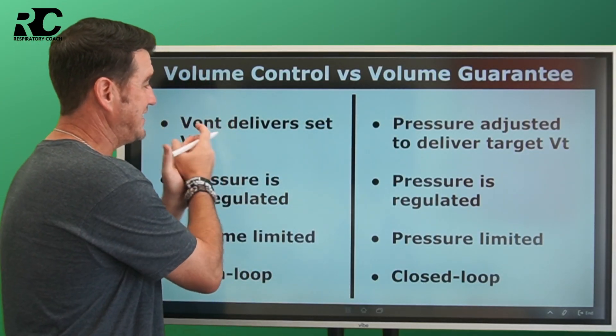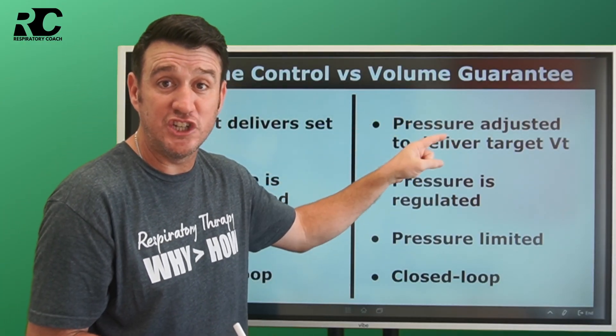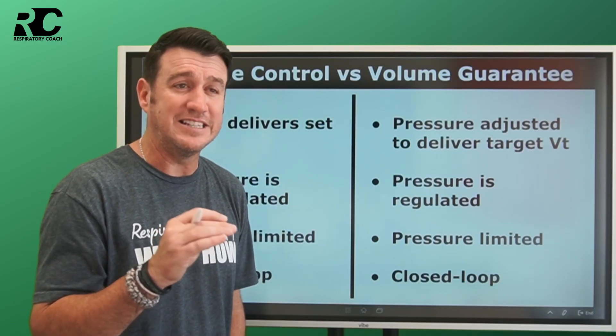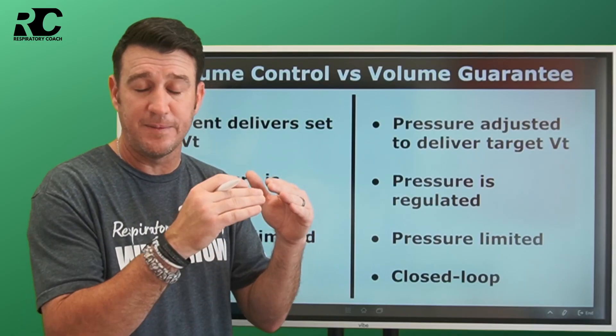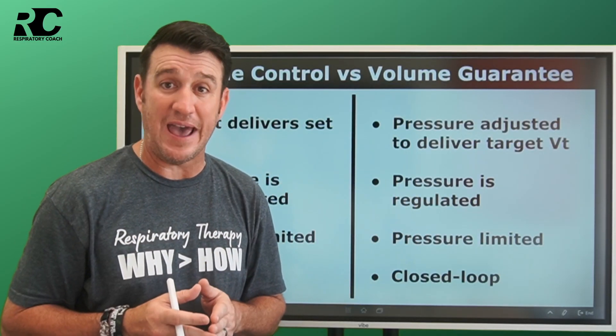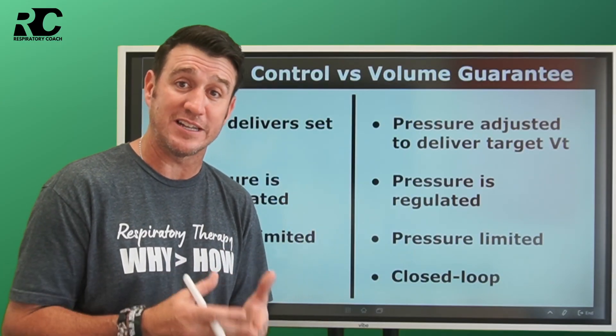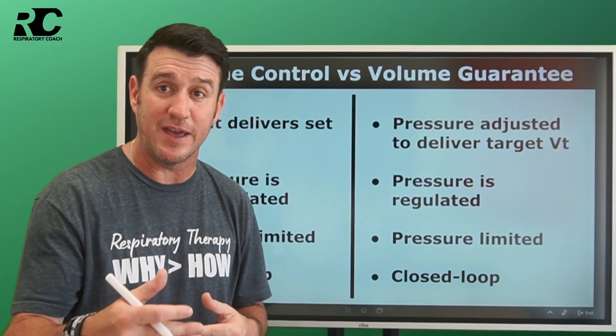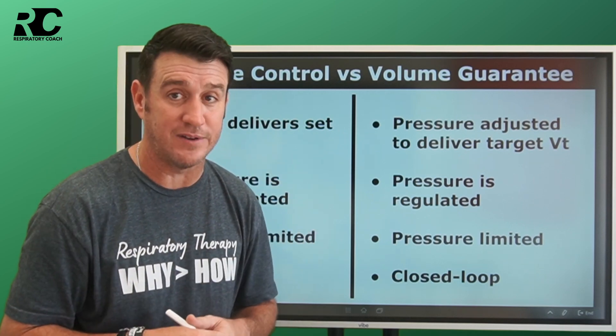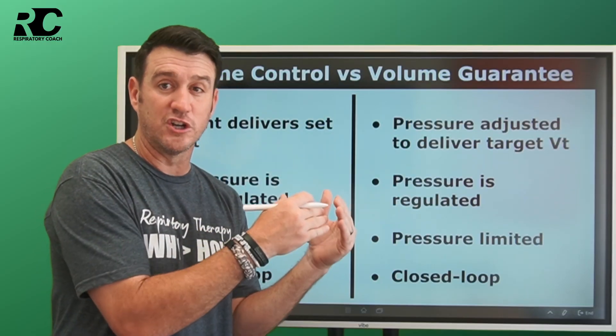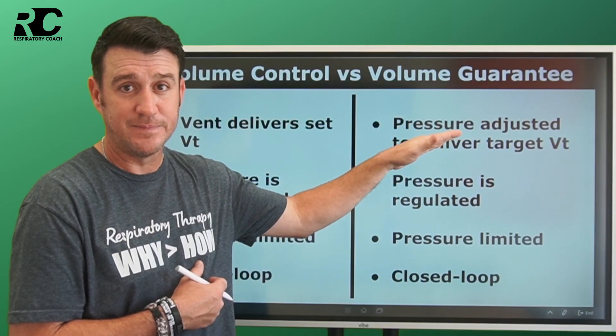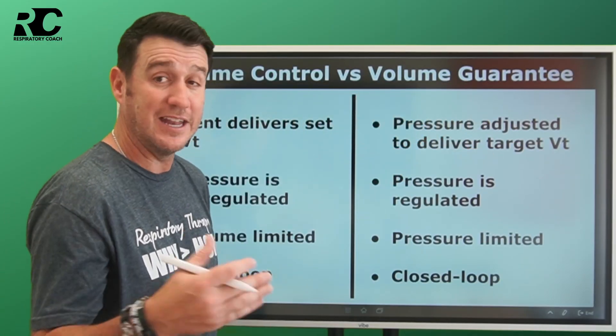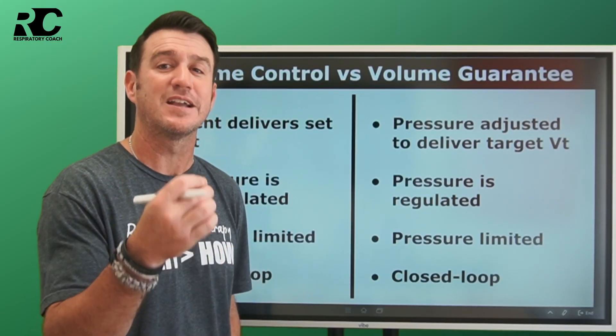Quick recap: volume control delivers the set tidal volume; volume guarantee automatically adjusts pressure to achieve the target tidal volume. Importantly, it doesn't adjust pressure during the breath — it waits for the exhaled tidal volume to come back before making a decision. If the exhaled volume is within the target range, it stays where it is. If pressure was increased and the volume comes back greater than target, on the next breath it turns the pressure down. It's constantly adjusting pressure to stay in that target range based on exhaled tidal volumes, which are driven by compliance and resistance.